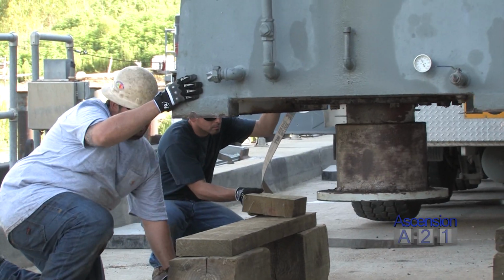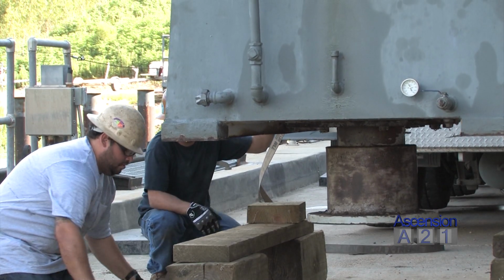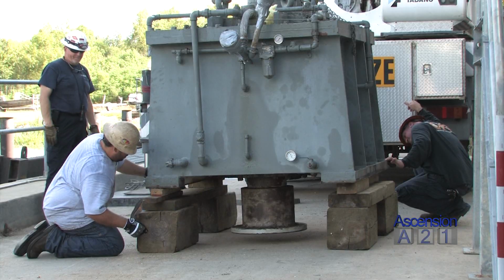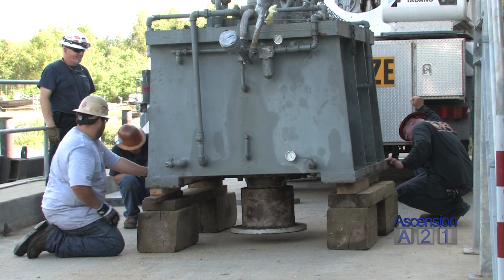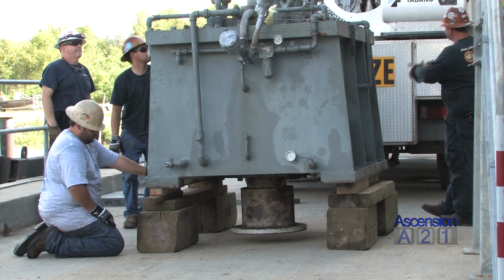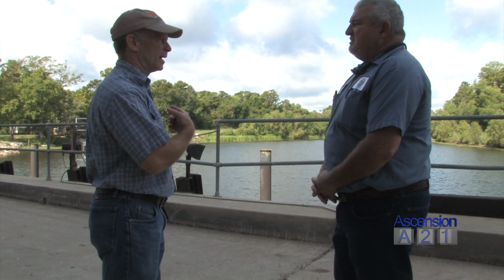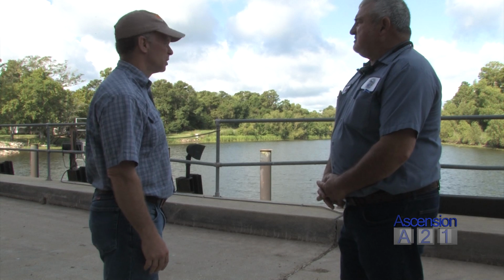The vibration analysis said it was an alignment issue. So we did have a company come in after the vibration analysis, and they lined it up the best they could with what they said needed to be done. We put it back to work. After 14 hours of service, it started vibrating tremendously. So we shut it down.